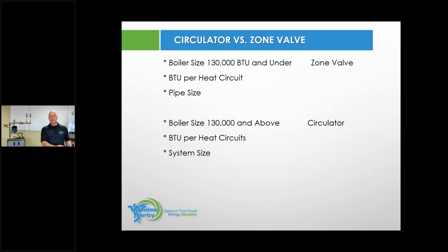And based on circulator curves and circulator capability, I don't think I ever want to have a zone valve system with greater than a 0010 circulator because of velocity. And if I get to anything larger than that, I'd have a bypass, and it just creates a lot more items to put in there. So, strictly geared around velocity and noise.